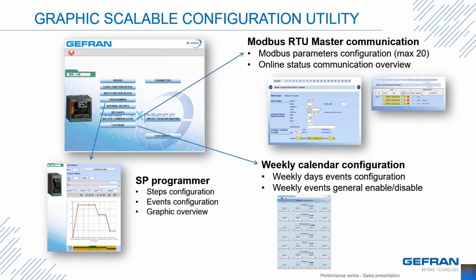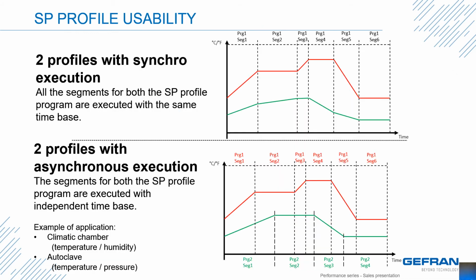There is a weekly calendar configurator. You can initiate control and start up certain functions with the weekly calendar. This is where you could set up ramp soak too. You can do it from the front panel, but I'd prefer the software because all the parameters are in front of you. And note that it gives you a graphical representation of your profile. As I mentioned, the ramp soak in GFX Express.